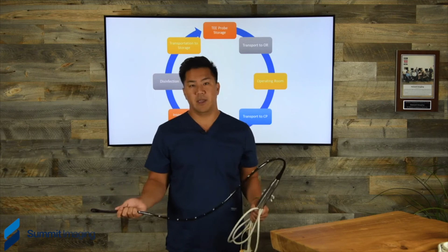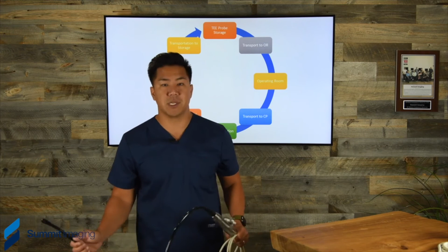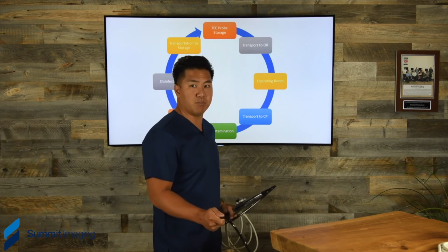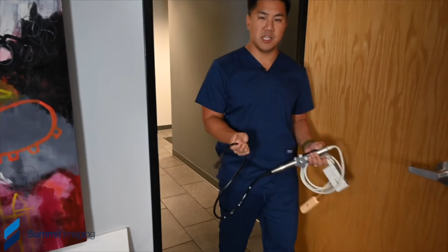So we recommend carrying it in a way where you can control it, with the idea that things aren't going to be swinging around unnecessarily, because if you carry it like this, you can risk banging it into a table. Another one is banging it into the side of doors as you're going in and out of rooms. So as we're transporting a TEE probe, it's important to protect the tip, because oftentimes accidental damage occurs when just transporting this probe around. For example here, door jambs are a TEE probe's worst nightmare. Now, that impact was completely on the tip against a metal door frame, and that will cause enough impact to damage all the microelectronics inside the head of the TEE probe.